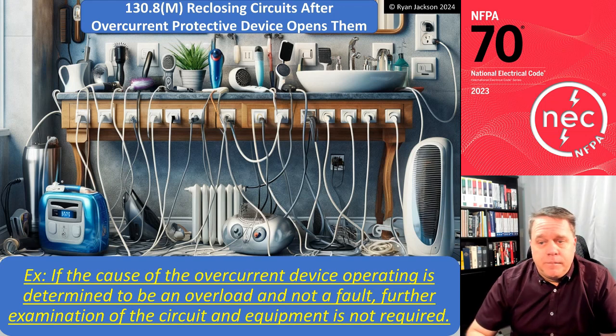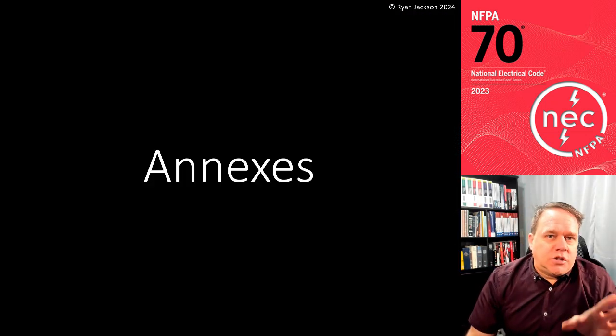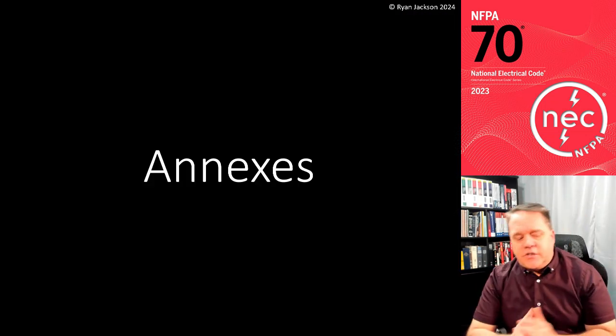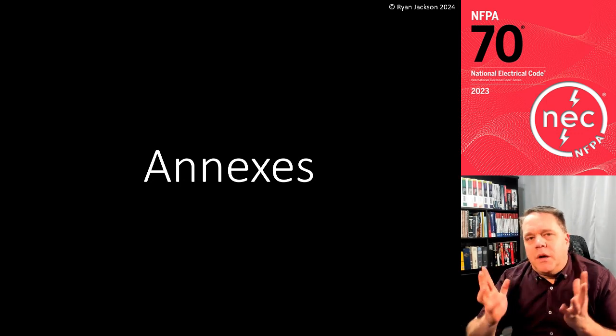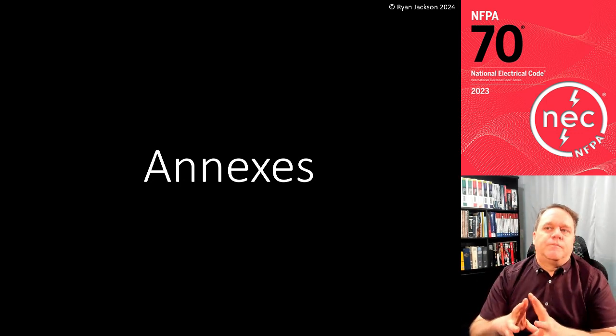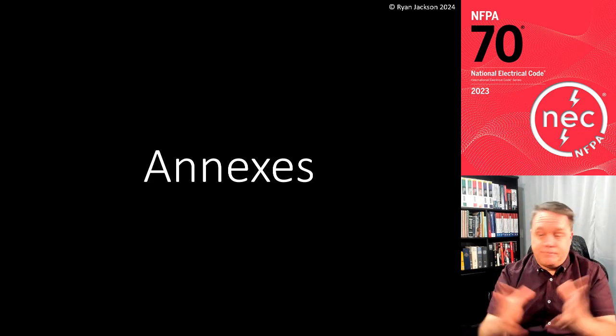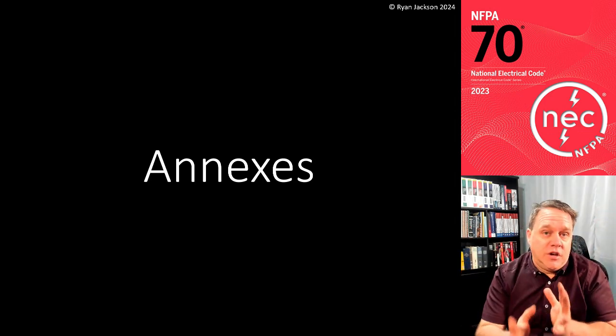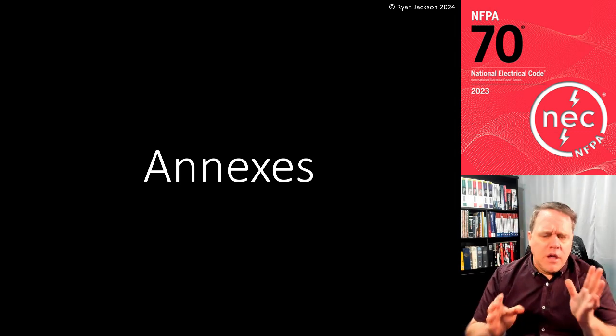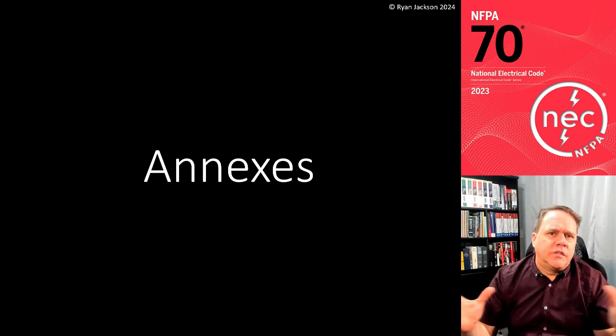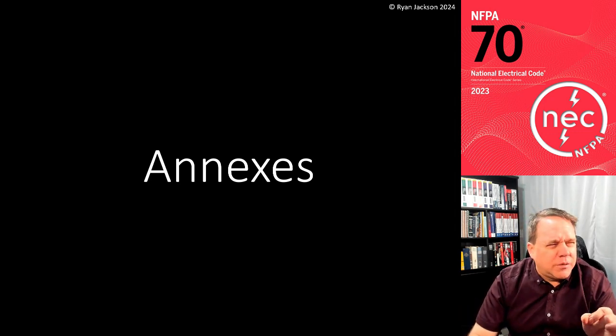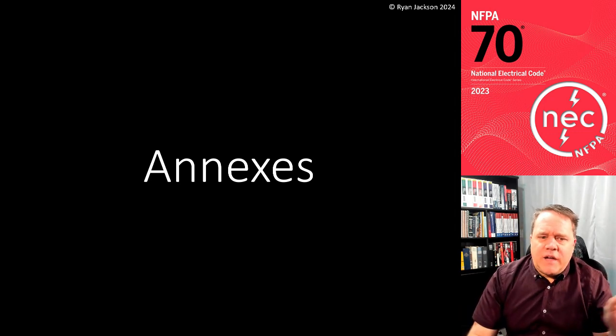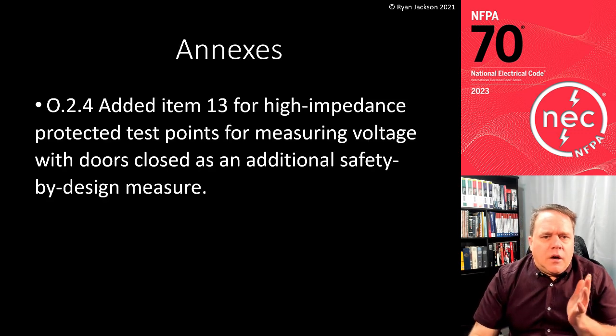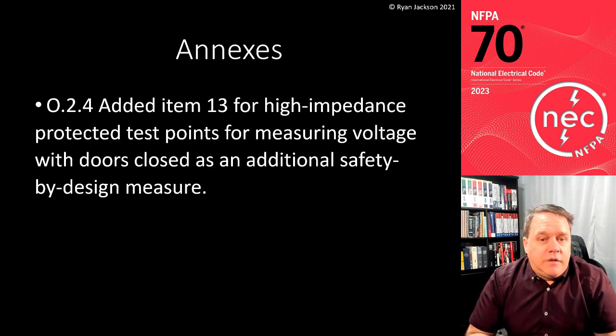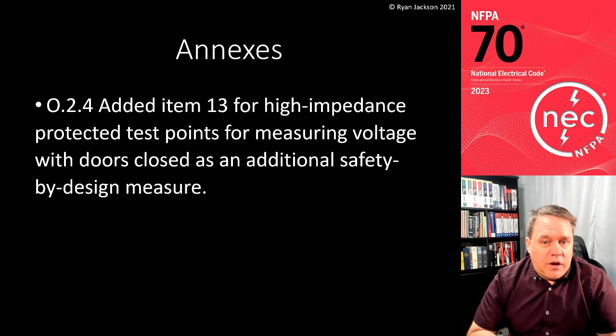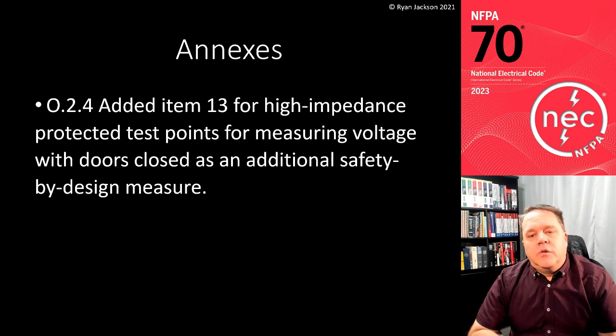The last change to talk about is in the annex materials. Yes, there were a couple of things in chapters 2 and 3, but not that many. And I want to keep this relevant to the people that work in several different locations, not just for batteries or capacitors, right? So if your world is capacitors and batteries and things like that in chapters 2 and 3, yeah, there were a couple of changes. But aside from that, annexes, O.2.4 added item 13 for high impedance protected test points for measuring voltage with doors closed as an additional safety by design measure.